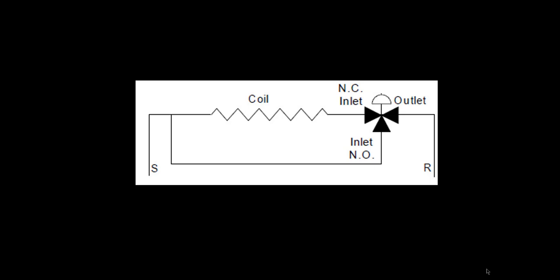A mixing valve can also be used in a bypass application to control the flow through the coil by placing the valve downstream of the coil. The flow through the coil is still controlled by the stem position of the mixing valve. The location of the three-way valve will not affect the operation of the system. In both scenarios, the valves are controlling the amount of flow to the coil.